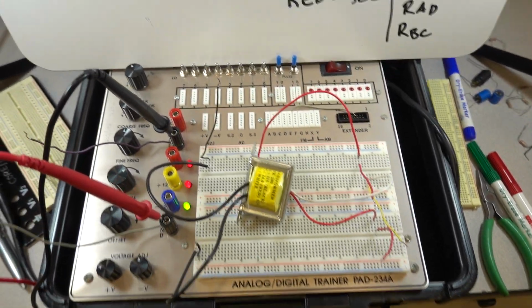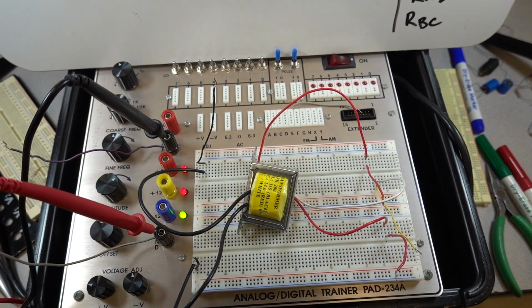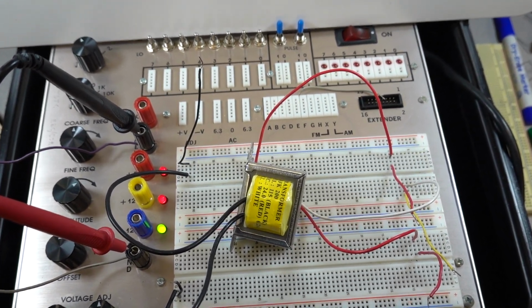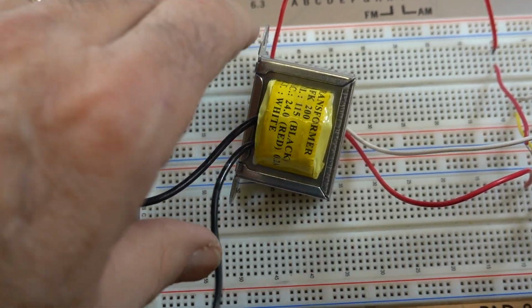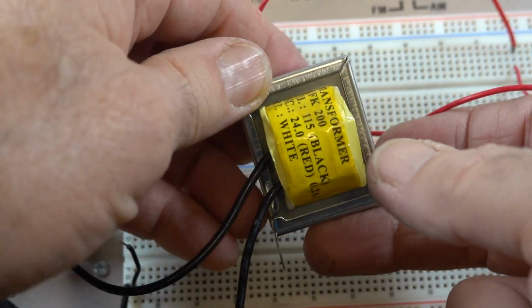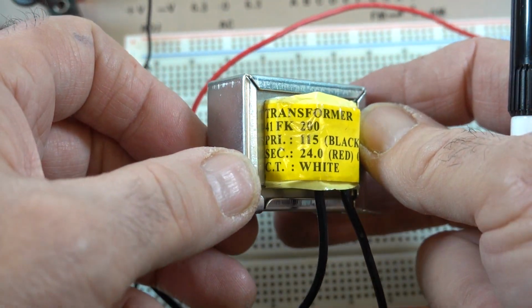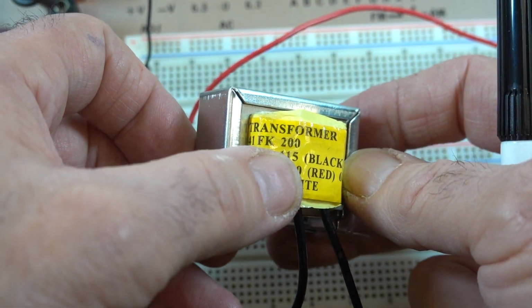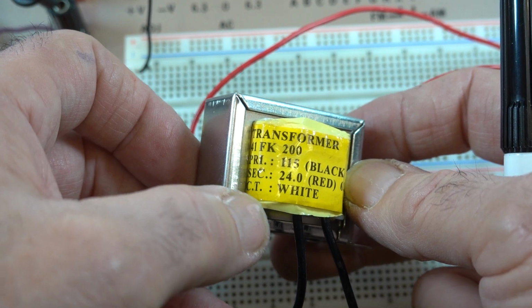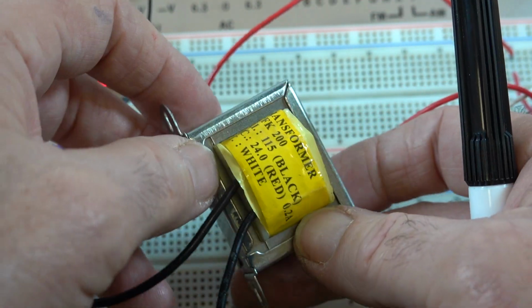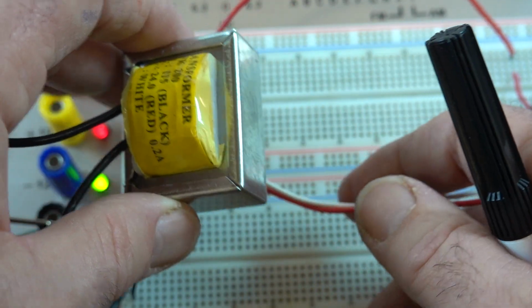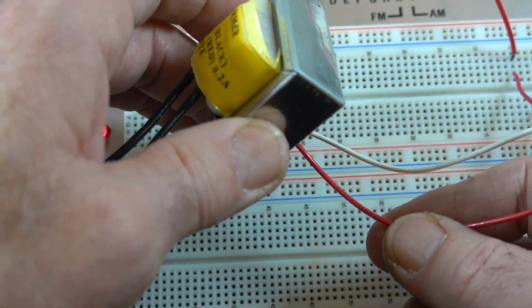We're going to look down here. Most transformers will have some labeling about what the input and output are. Looks like the input here is 115, output's 24, and the CT over there says white. So that's how our transformer is set up.